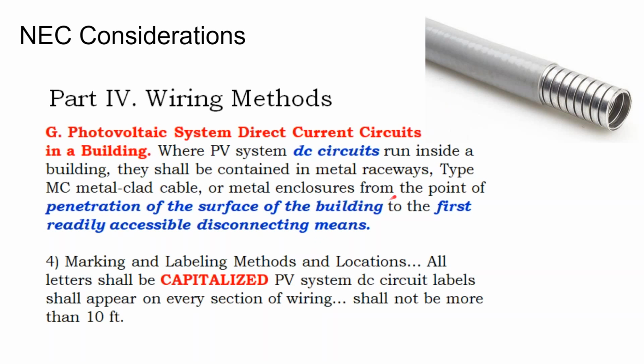You can't just put that connection to ground anywhere in the system. It has to be at the one point where the neutral of your electric service is connected to ground. And usually that neutral to ground connection is done inside your utility meter. So it's not apparent to anyone who's not in the electrical industry. But that little neutral is a drain for your electricity. And so your electric usage ultimately needs that neutral to ground connection. And so they say, well, on that other side of that main bonding jumper, you need your grounding electrode. Well, there's also a call out for a secondary grounding electrode. So 2 grounding electrodes. They can be right next to each other.